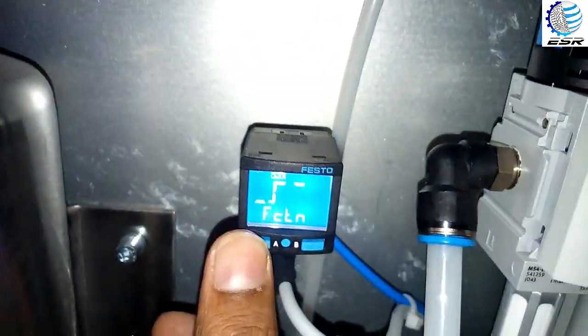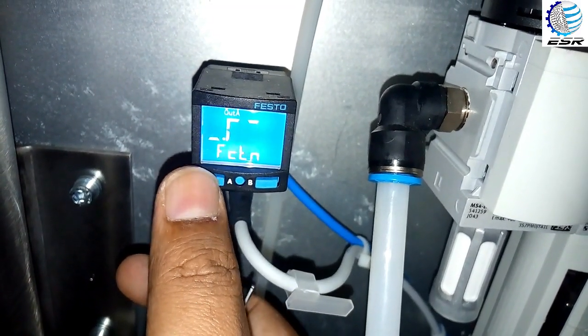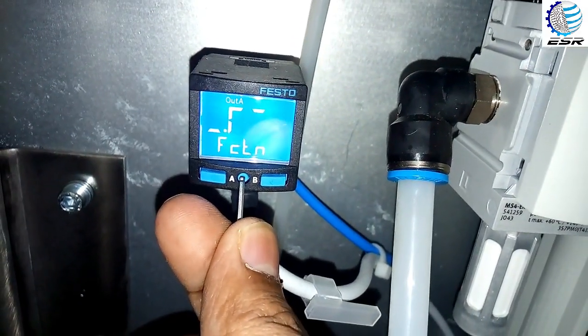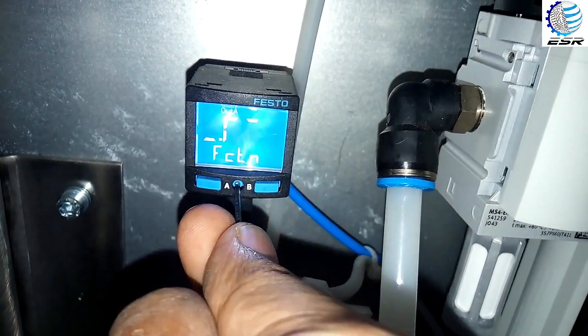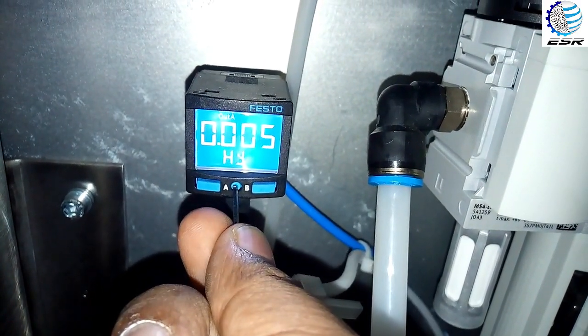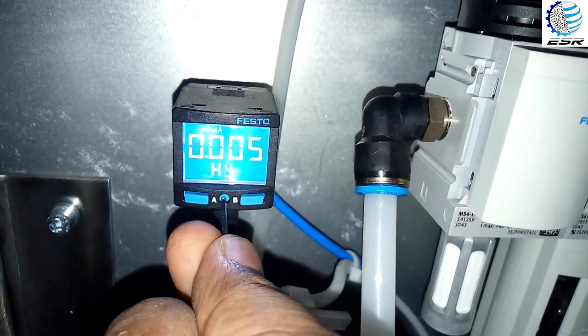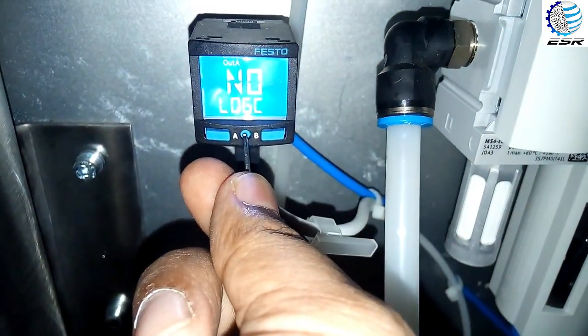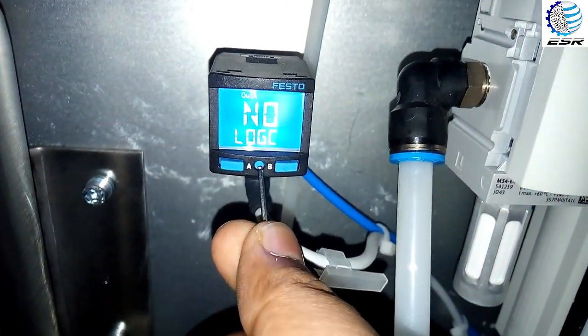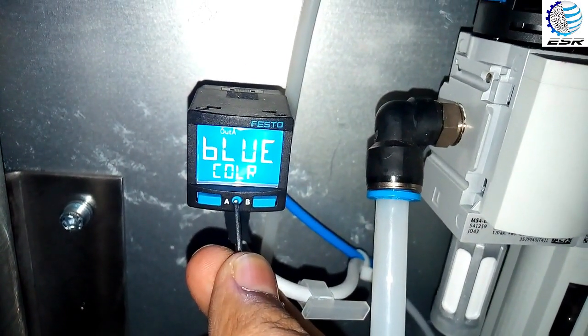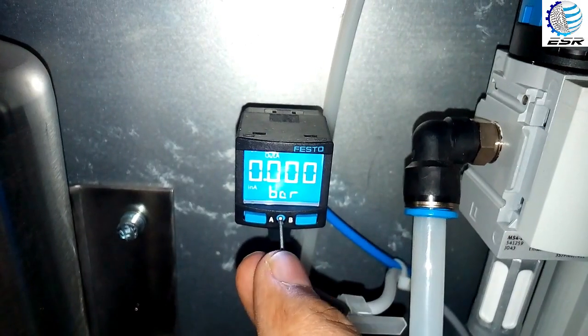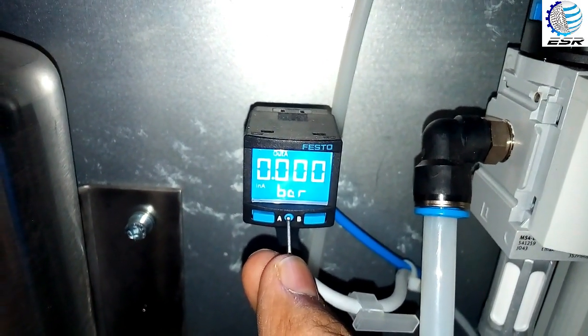We can change the value from here, but since we only need this specific function for this application, we will leave it as is and press forward. The set point value is 0.6 bar and the hysteresis value is 0.005 bar. The logic is set to normally open — you can set it to normally closed according to your requirement. The color will be set to blue.